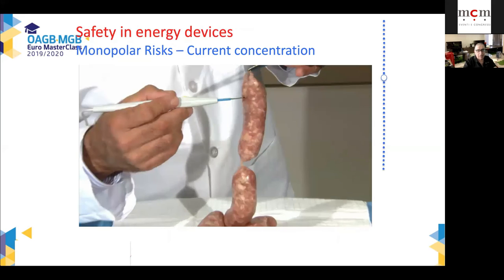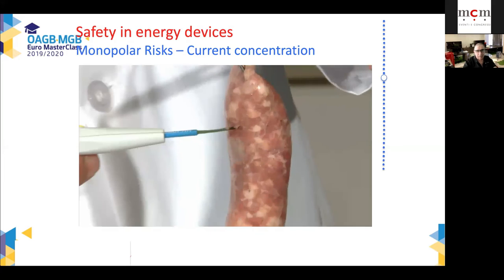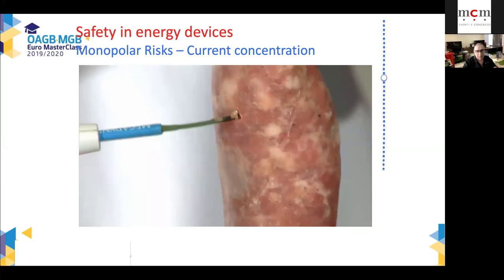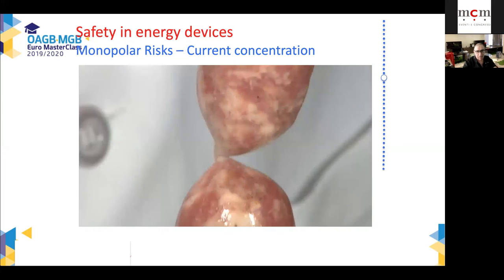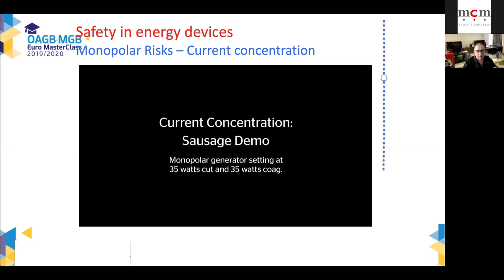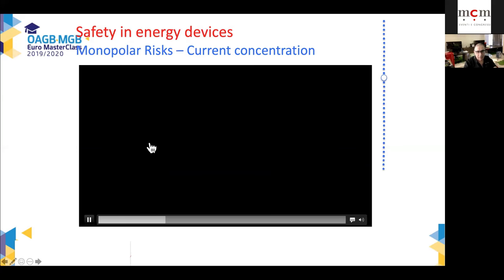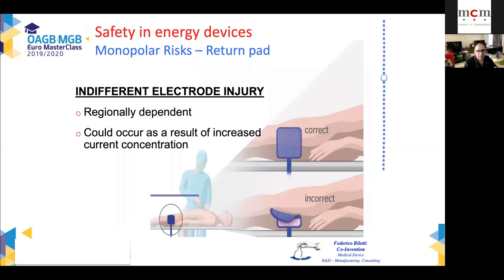Concentration of current causes more damage than contact with monopolar devices. Where you expect the damage to appear is not the highest damage. Look at what happens where the surface is reduced. You have the disconnection of the tissue. What this means is that you may be unknowingly causing damage where organs are touching each other in a small surface. There, the higher damage will happen than where the monopolar device is touching the organs.